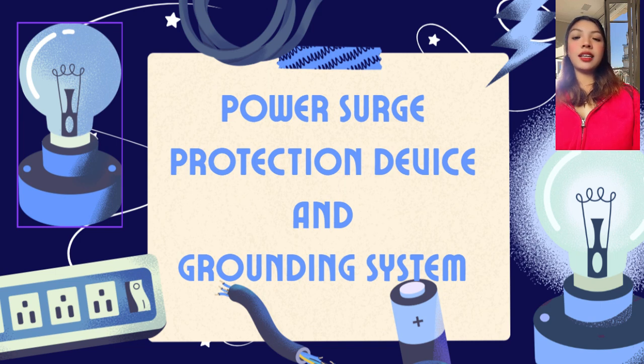So this presentation discusses power surge protection devices, or SPD, and grounding systems, which are essential in protecting electrical systems and equipment. In any electrical installation, sudden increases in voltage called surges can damage appliances, disrupt operations, and even cause safety hazards. These surges can come from internal sources like switching operations or external sources like lightning strikes. To prevent damage, engineers use surge protection devices, or SPD, to control and limit excess voltage, and grounding systems to safely discharge unwanted electrical energy into the earth. Understanding these concepts helps ensure system reliability, equipment protection, and human safety.